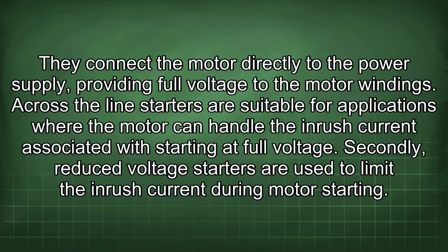They connect the motor directly to the power supply, providing full voltage to the motor windings. Across-the-line starters are suitable for applications where the motor can handle the inrush current associated with starting at full voltage. Secondly, reduced voltage starters are used to limit the inrush current during motor starting.